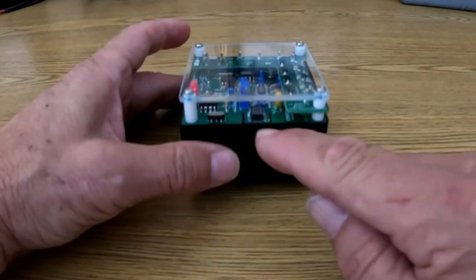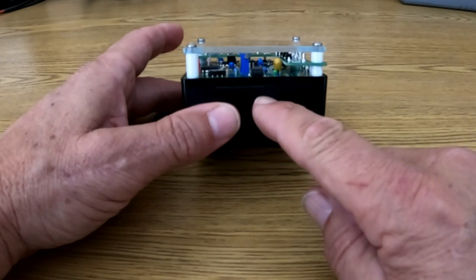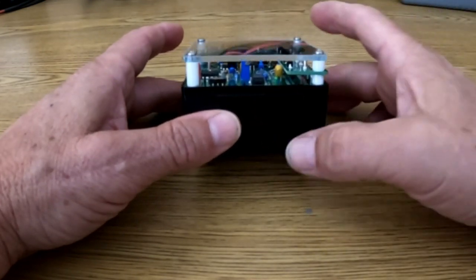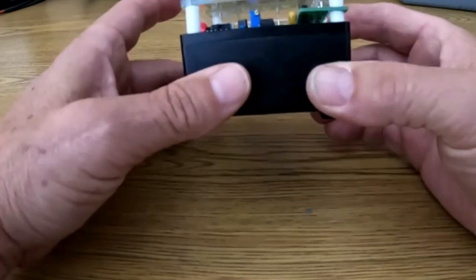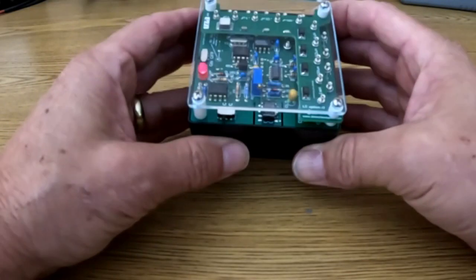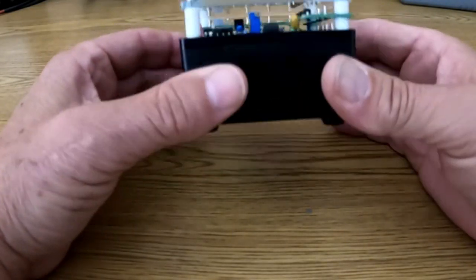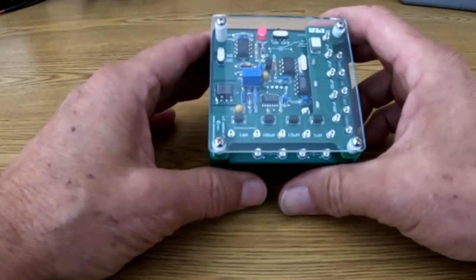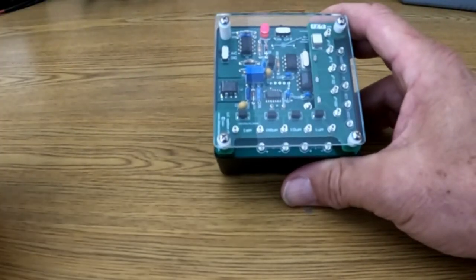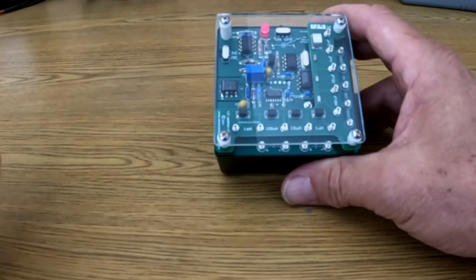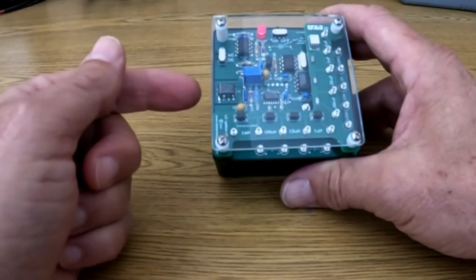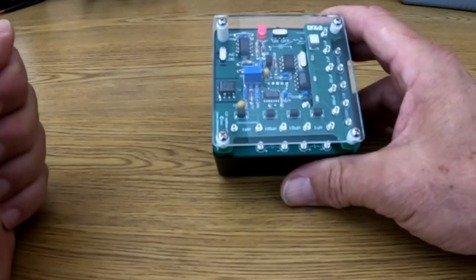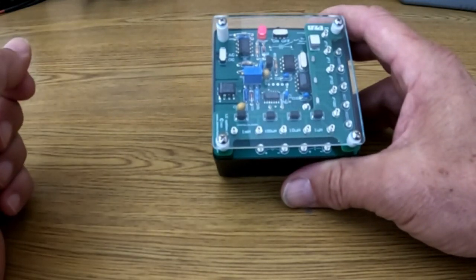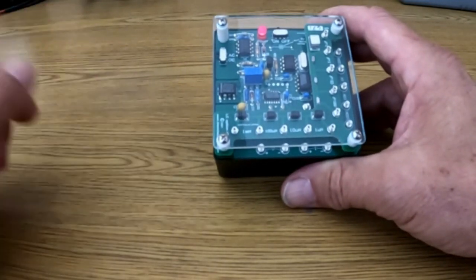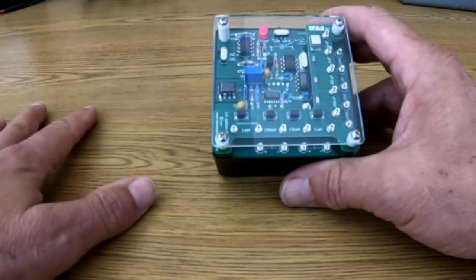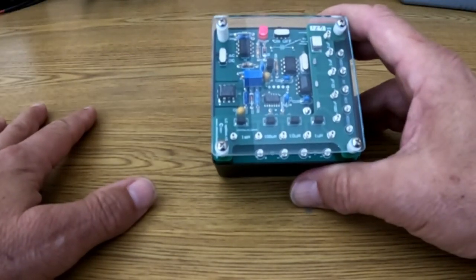The LT1021 5-volt reference, the same one used in some very high-end pieces of test equipment, is exposed to ambient air and is also static sensitive. So when people would send this in for calibration — and by the way, we offer free calibration within the first 2 years, you just pay for shipping — if they got their fingers in there after rubbing their feet on the carpet, they could zap that LT1021 and it would be no good. They would send them in for recalibration, and we would end up replacing that IC chip.